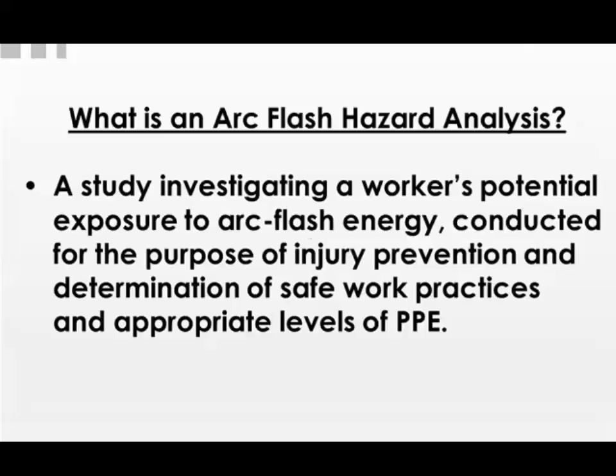So it's important to make sure that you implement arc flash safety at your facility and do an arc flash hazard analysis. An arc flash hazard analysis is an in-depth study investigating a worker's potential exposure to arc flash energy, conducted for the purpose of injury prevention and determination of safe work practices and appropriate levels of personal protective equipment. It's a methodical, detailed, step-by-step analysis done by an electrical engineer or somebody with an equivalent background, evaluating each piece of equipment in your plant for the potential for an arc flash, and making sure it's safe and meeting the NFPA, National Fire Protection Association, and NEC, National Electrical Code, guidelines.